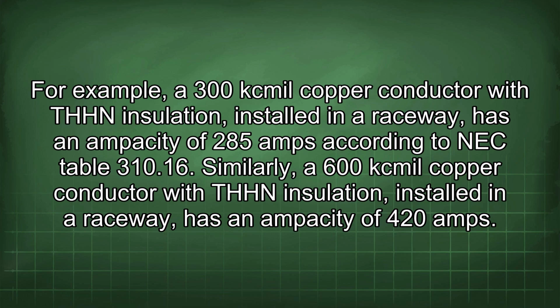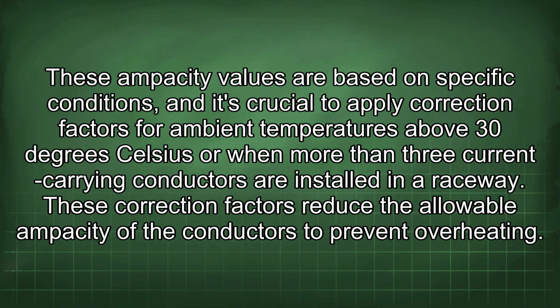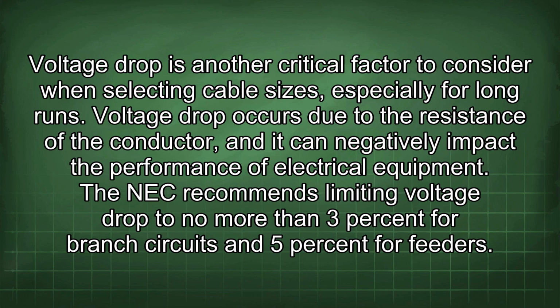These ampacity values are based on specific conditions, and it's crucial to apply correction factors for ambient temperatures above 30 degrees Celsius or when more than 3 current-carrying conductors are installed in a raceway. These correction factors reduce the allowable ampacity of the conductors to prevent overheating. Voltage drop is another critical factor to consider when selecting cable sizes, especially for long runs.